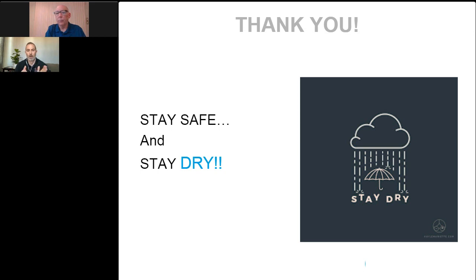Right. Well, with that said, why don't we get to a couple of questions? We have quite a few here, some good ones. Can using forced air for drying cause damage to the robotic devices? That is a great question. So you want to make sure, as always, to check with the manufacturer IFU. You also want to make sure that you're working with your facilities engineers in your hospital to make sure that the pressure that's coming either out of the tank or the wall is appropriate for the devices that you're attempting to blow air through.